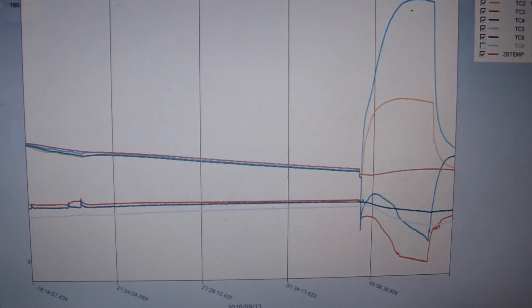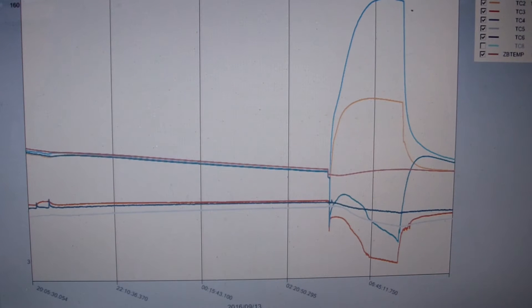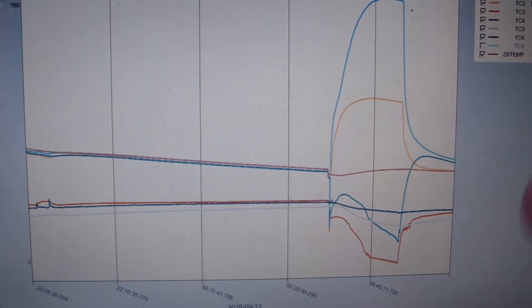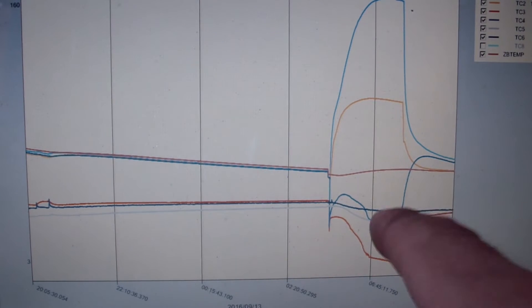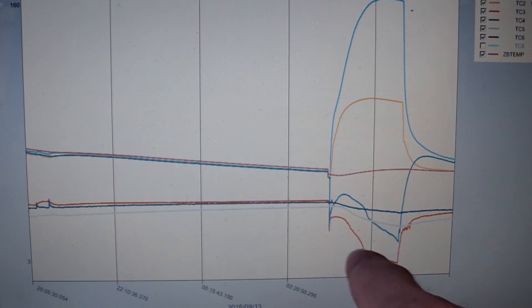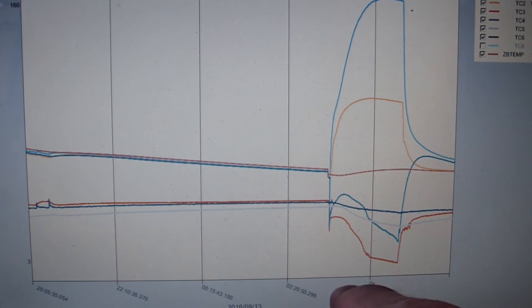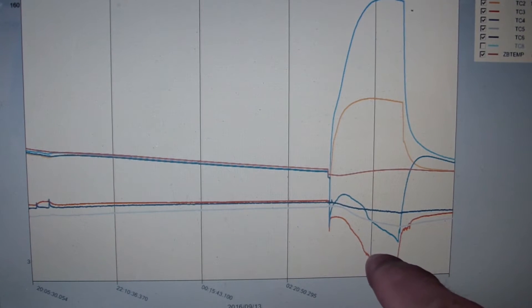This morning it ran for about two hours there. I added a little bit of refrigerant just here a moment ago because as you can see, the superheat took almost an hour to really drop down to saturation there.